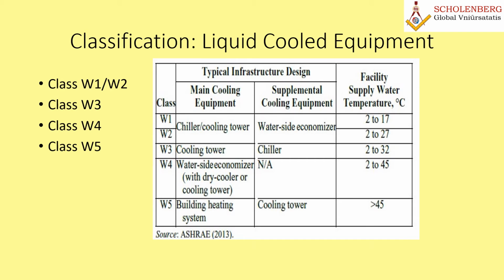Well, this is for the very huge data center with huge load density. Then the use of chillers comes into the picture. But these are rarely found, and only in the US or some parts of Europe where you have a huge load density. Let's come to class W3. For most locations, these data centers may be operated without chillers, although some locations require chillers. Class W4 is the class to take advantage of energy efficiency and to reduce capital expenses. These data centers are operated without chillers.